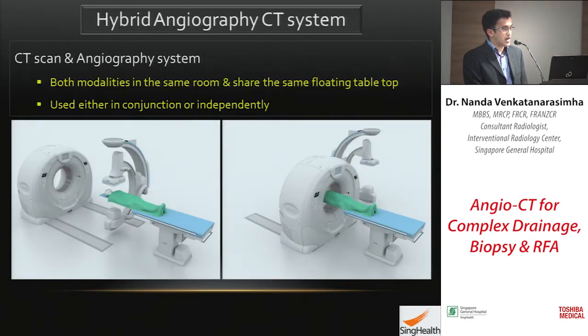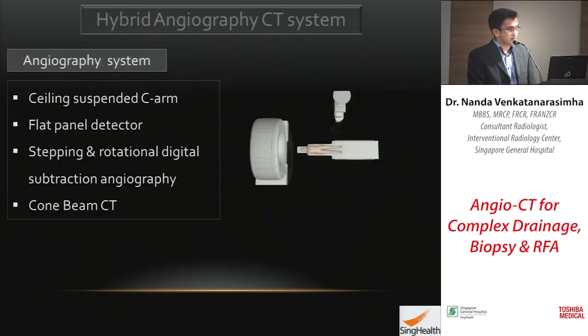So it's a hybrid Angio-CT system, which is a combination of two modalities in the same room, which share the same floating tabletop. They can be used either in conjunction or independently. So the angiography system has got a C-arm, which is suspended from the ceiling, and a flat panel detector, and can perform both stepping and rotational digital subtraction angiography, and is also capable of cone beam CT.